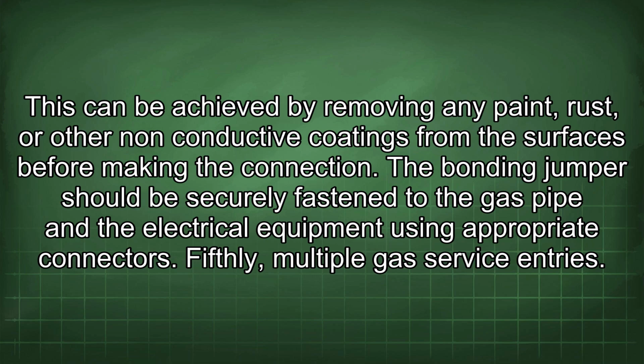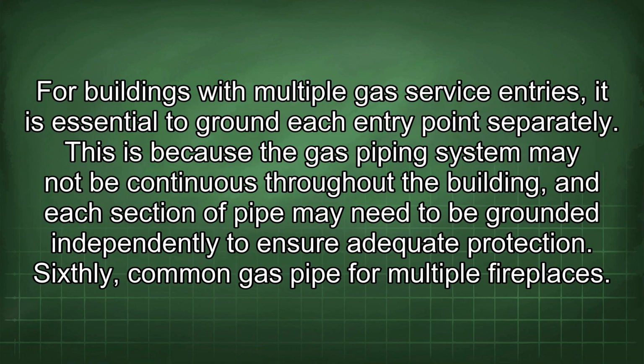Fifthly, multiple gas service entries. For buildings with multiple gas service entries, it is essential to ground each entry point separately. This is because the gas piping system may not be continuous throughout the building, and each section of pipe may need to be grounded independently to ensure adequate protection.